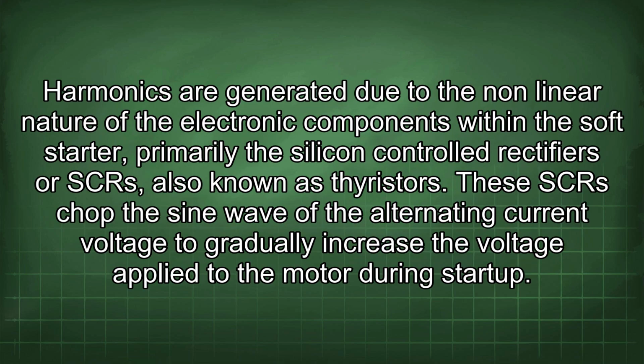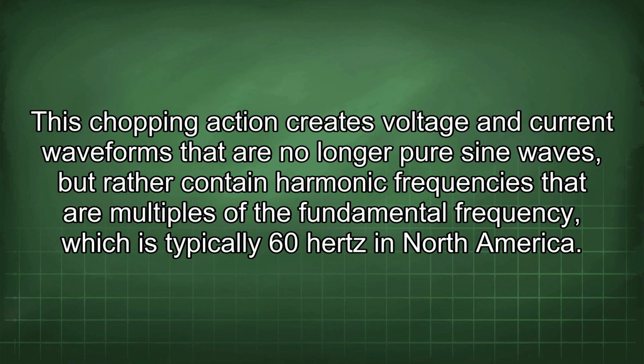Harmonics are generated due to the nonlinear nature of the electronic components within the soft starter, primarily the silicon-controlled rectifiers, or SCRs, also known as thyristors. These SCRs chop the sine wave of the alternating current voltage to gradually increase the voltage applied to the motor during startup. This chopping action creates voltage and current waveforms that are no longer pure sine waves, but rather contain harmonic frequencies that are multiples of the fundamental frequency, which is typically 60 Hz in North America.